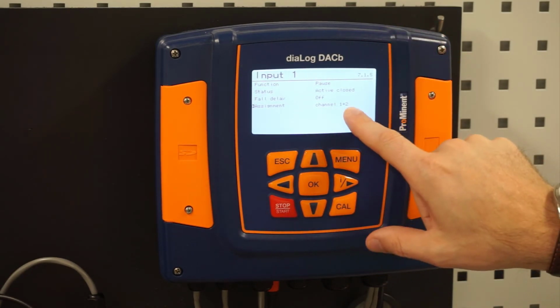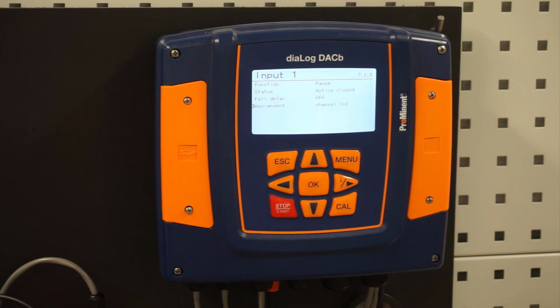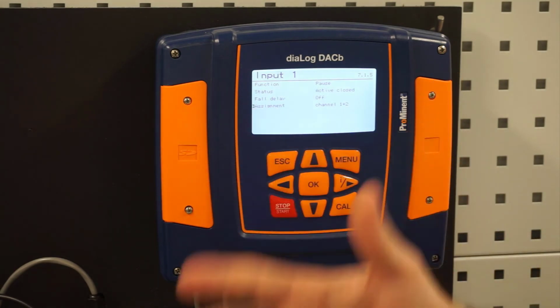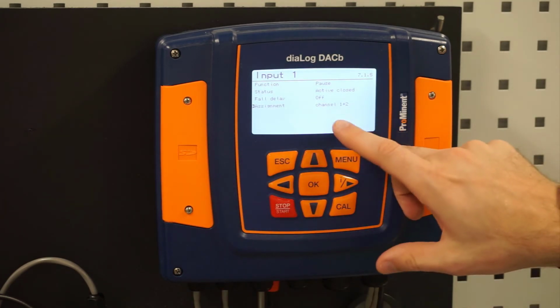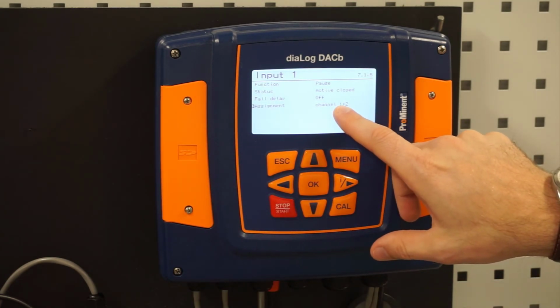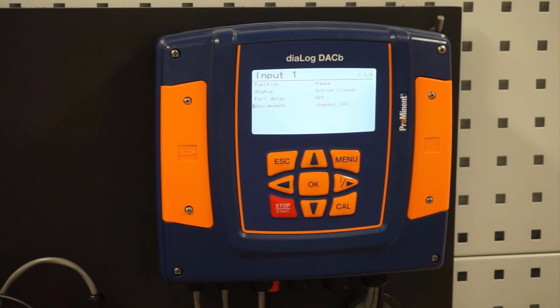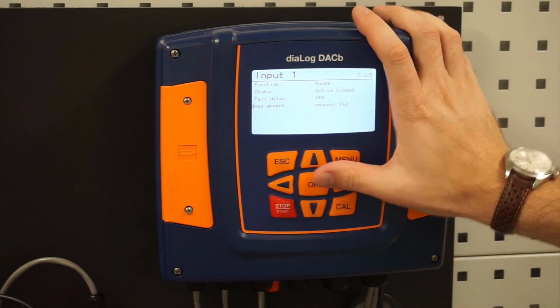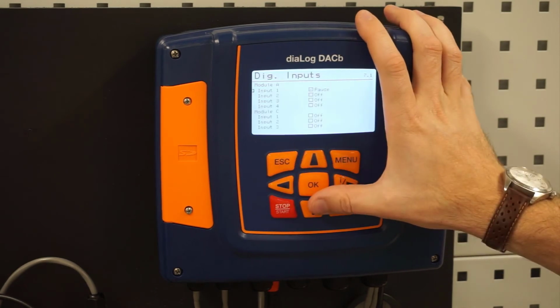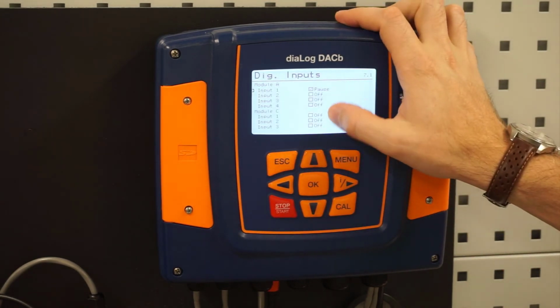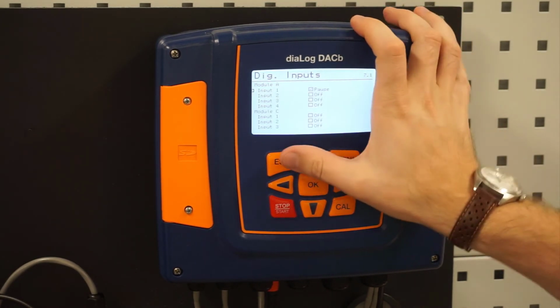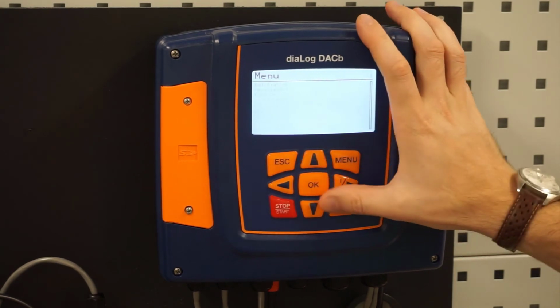You can also make sure it's assigned. We would want it to shut down our control both on channel 1 and 2. That is if we were pumping a chemical from both channels. Right now we are only controlling from 1. We do not have a chlorine pump set up, but we would most likely have that set up if we're doing free chlorine. You can see there is 7 of them there. I showed you where those were on the boards.